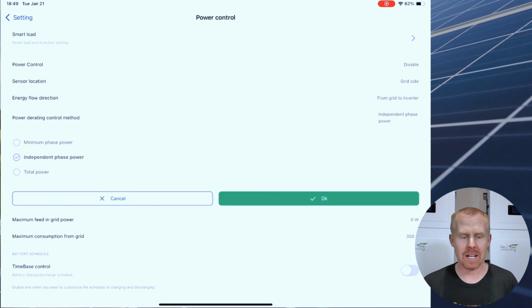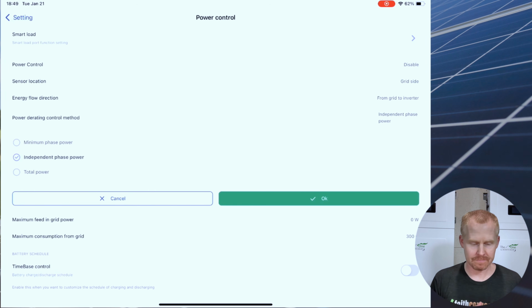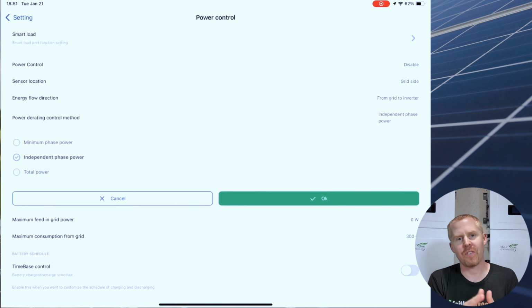The power derating control method, I'm going to take a shot in the dark at this one. It allows your inverter to control the power based on the minimum phase power, the total power from both phases, or looking at the independent phase power to determine how it can derate. And by default, it's going to be the independent phase power. You want it to look at each phase independently of the other.